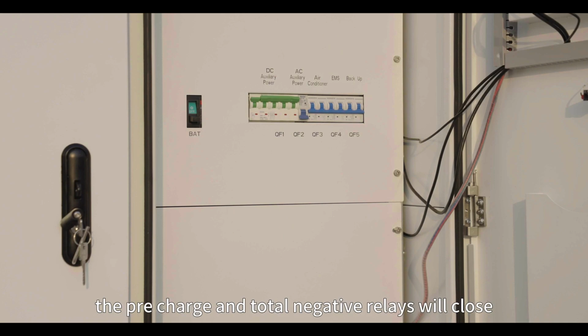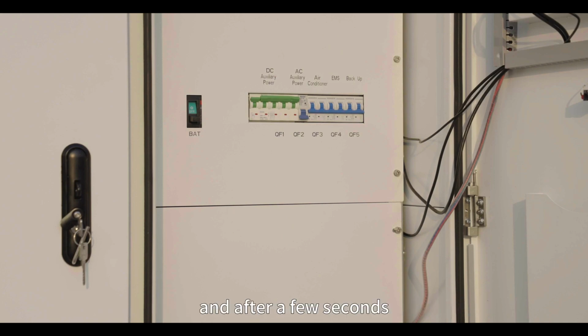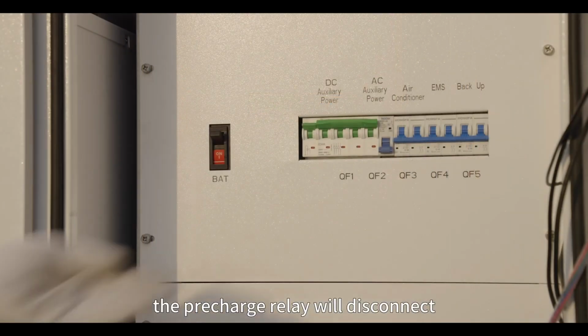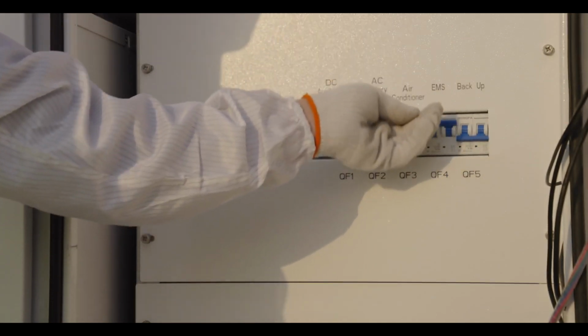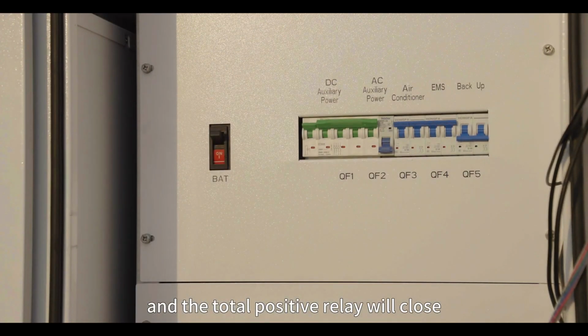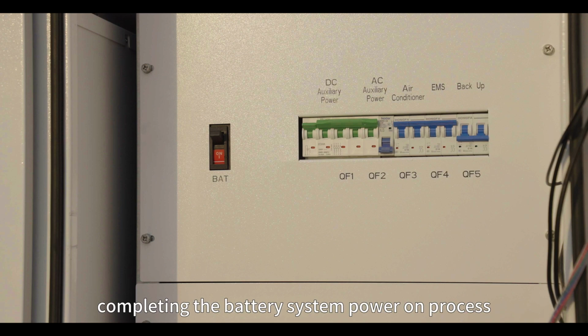The pre-charge and total negative relays will close on the upper computer, and after a few seconds, the relays will actuate for the second time. The pre-charge relay will disconnect, and the total positive relay will close, completing the battery system power-on process.